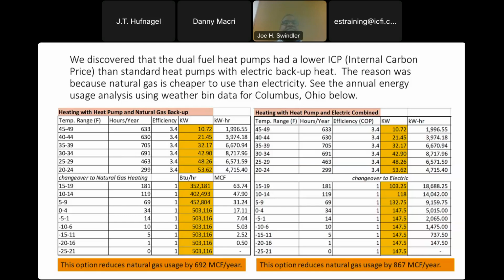Heating with a heat pump with natural gas backup reduced natural gas usage by 692 MCF per year. And then if you eliminate natural gas as backup when it's very cold, it reduces natural gas usage even more, by 867 MCF per year. But that's a large amount of natural gas. As you can see, with the dual fuel heat pump, you still have a very significant amount of natural gas reduction per year. So that's what the analysis showed us. You don't eliminate all the natural gas, but you eliminate about 80% of the natural gas usage. Everybody wants to decarbonize 100%, but sometimes it gets very expensive. Next slide.